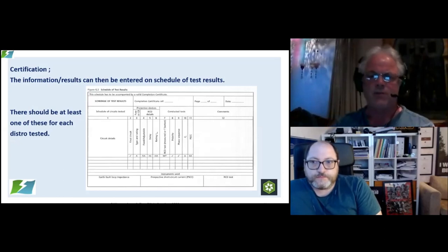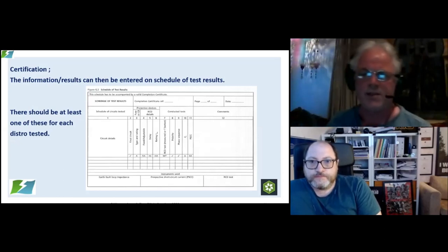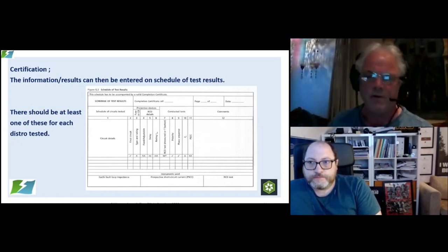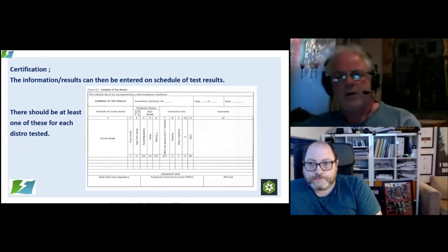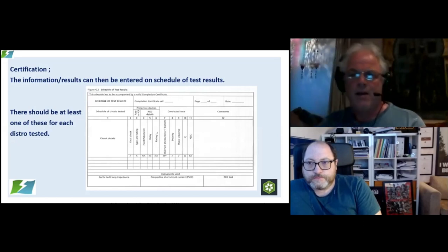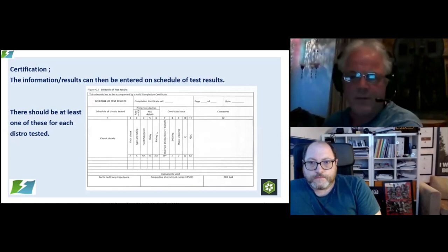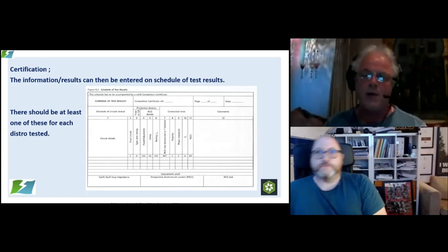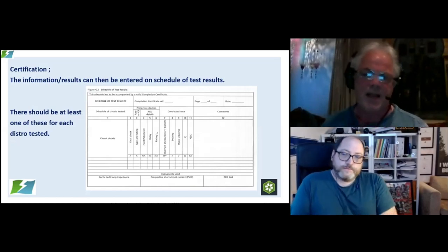So if we've got three of those plugged into a piece of distro, and we've got an earth loop of X amount at the distro, and Y amount at the end of the circuit, once we know those lengths, we should be able to say it should be about that much. When we do a test, we're verifying. We get an earth loop impedance reading, but we're also verifying the continuity and the connections all the way through. If we get a high reading, we know there's an issue. And this, again, comes with experience.